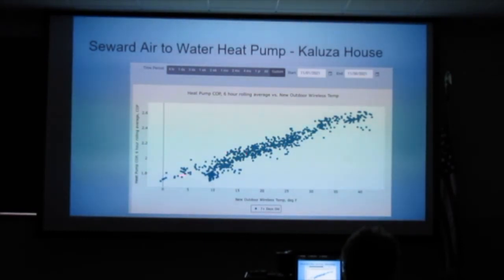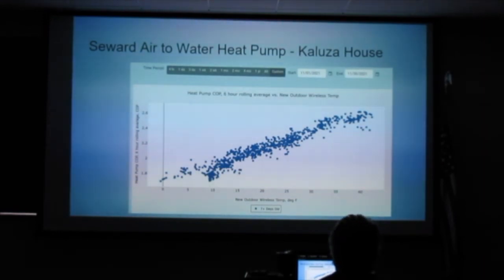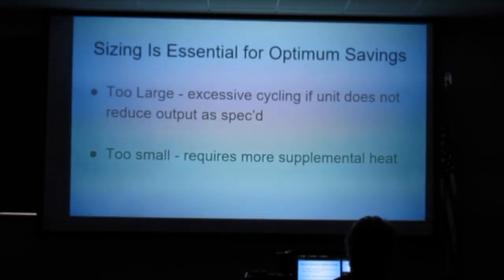This is my air-to-water heat pump, just in the last November. We went from the high 40s down to below zero for a few hours out of the year. Again, there's that efficiency line, and this is the COP here. This is where it starts getting a little iffy in terms of pure economics. With $3.30 oil... at $4.50 oil, I would just let it run because it's still going to be significantly cheaper.